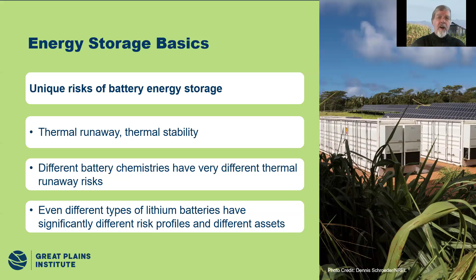These different battery energy storage systems also have different safety standards already designed. The primary one to think about is the National Fire Protection Agency NFPA 855 standard, which sets a lot of the testing and safety standards for batteries and has been integrated into other safety standards, like the International Fire Code, which uses NFPA 855. The 855 standard has requirements like fire suppression systems, containers the batteries must be in, training requirements for operators, and notification requirements. Batteries under that standard have to meet certain testing requirements to validate their legitimacy and safety. So this is the key standard to keep in mind.